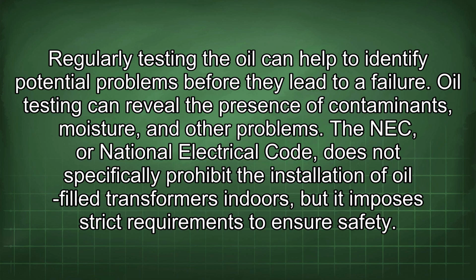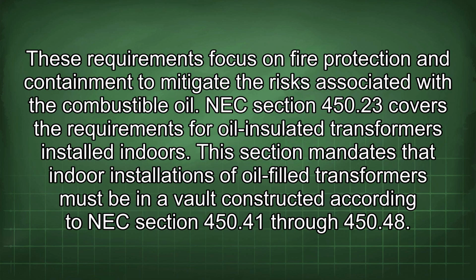The NEC, or National Electrical Code, does not specifically prohibit the installation of oil-filled transformers indoors, but it imposes strict requirements to ensure safety. These requirements focus on fire protection and containment to mitigate the risks associated with the combustible oil. NEC Section 450.23 covers the requirements for oil-insulated transformers installed indoors.